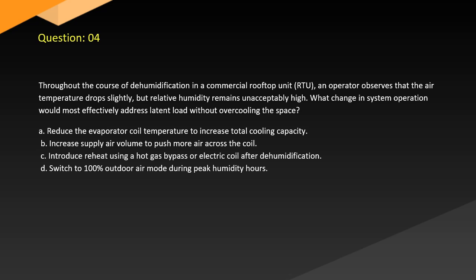A. Reduce the evaporator coil temperature to increase total cooling capacity. B. Increase supply air volume to push more air across the coil. C. Introduce reheat using a hot gas bypass or electric coil after dehumidification. D. Switch to 100% outdoor air mode during peak humidity hours.